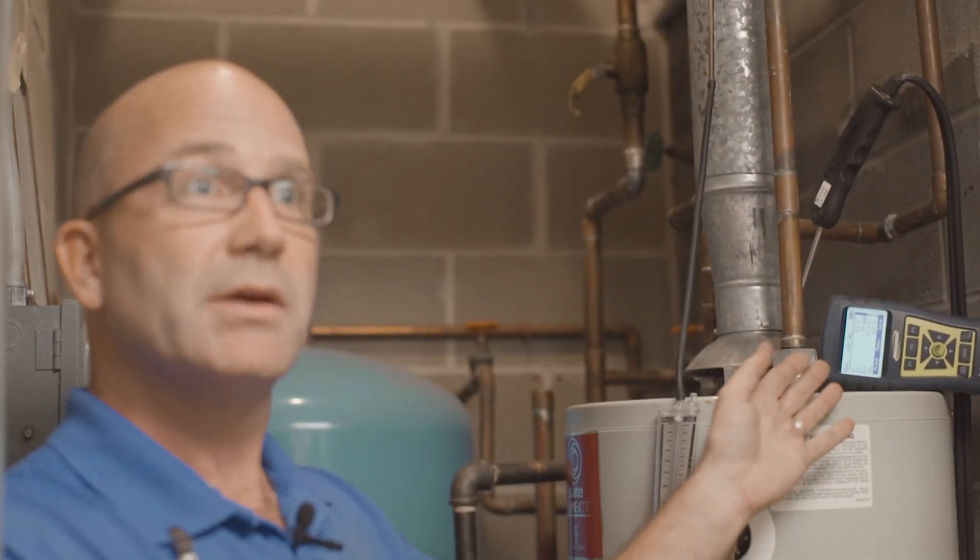I'll check gas pressure. I'll do a visual on the heat exchanger to see if it's rotted. We've caught a lot of heat exchangers just by simply doing this and being proactive about it versus reactive.